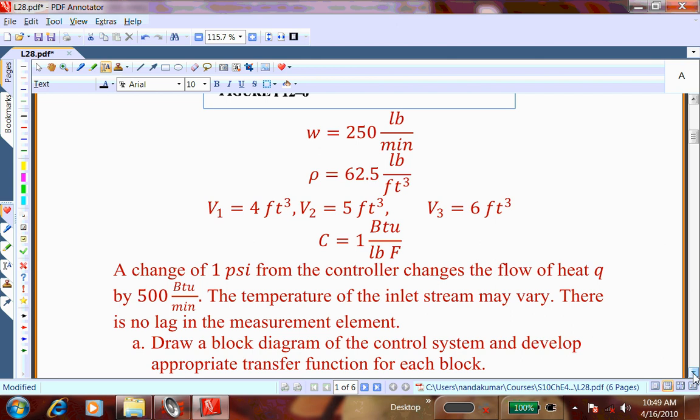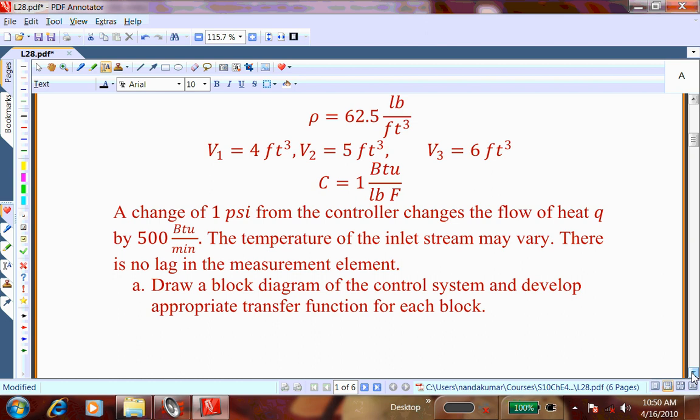The controller sends a pneumatic signal as a pressure change. If the pressure changes by one PSI, the heater increases heat input by 500 BTU per minute. The temperature of the inlet stream TI may vary. There is no lag in the measurement element, so there is no transfer function for that. We need to draw a block diagram for the control system and develop the appropriate transfer functions for each block — that is a fairly long process.